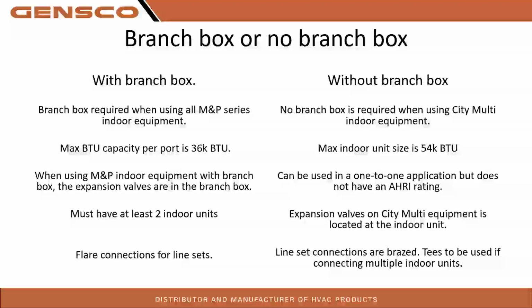When using M&P, we talked about the expansion valves. A couple of other things different that I want to mention is the expansion valve positioning. That's one of the big differences between City Multi and M&P. One, your expansion valves are in the branch box. Two, on M&P, your expansion valves have about 500 different positions available for metering, whereas without a branch box, when you're using City Multi indoor equipment, you have about 2,000 positions available. So the way the system meters is quite a bit different.